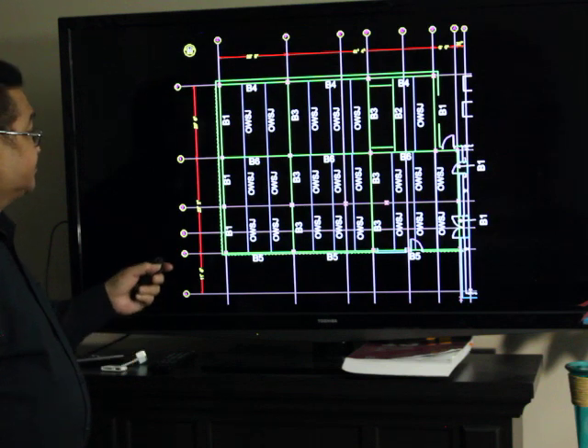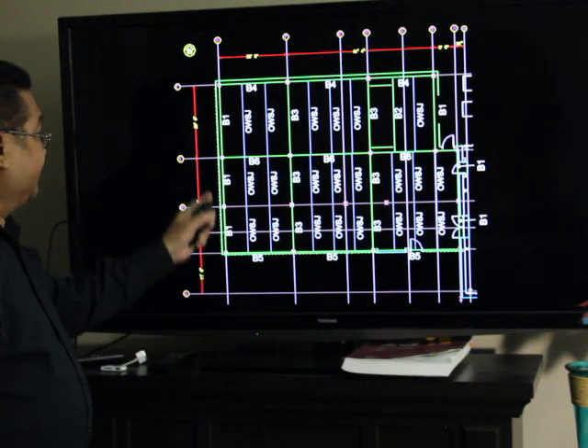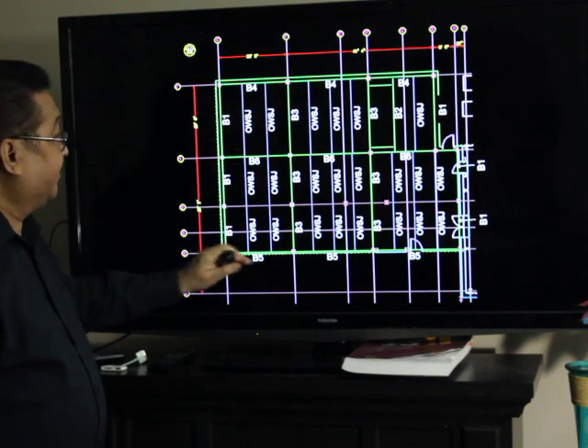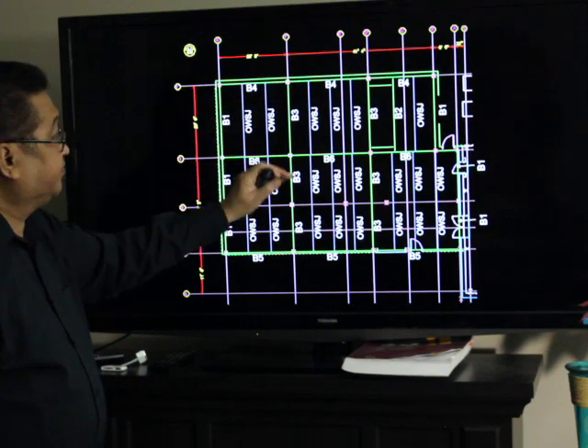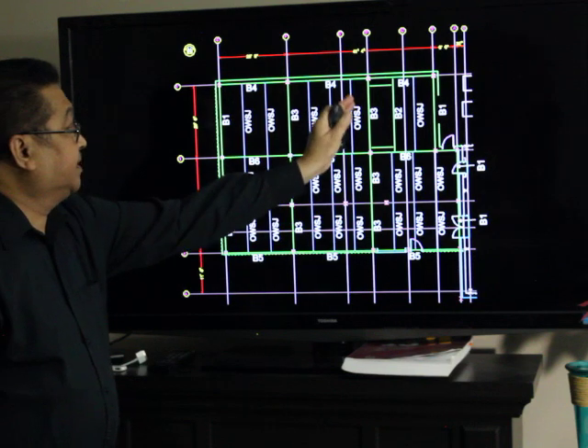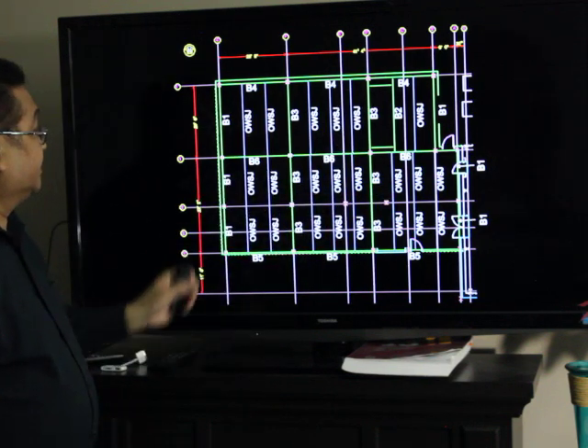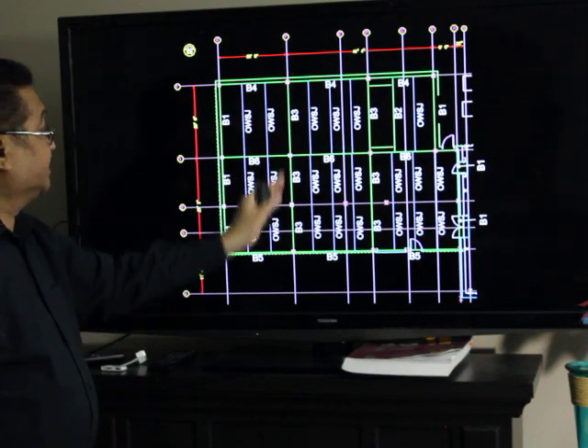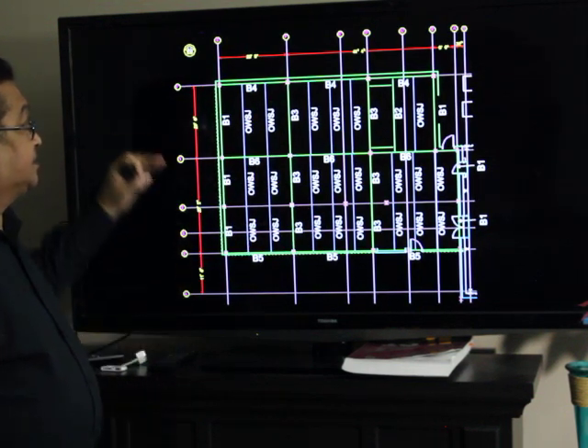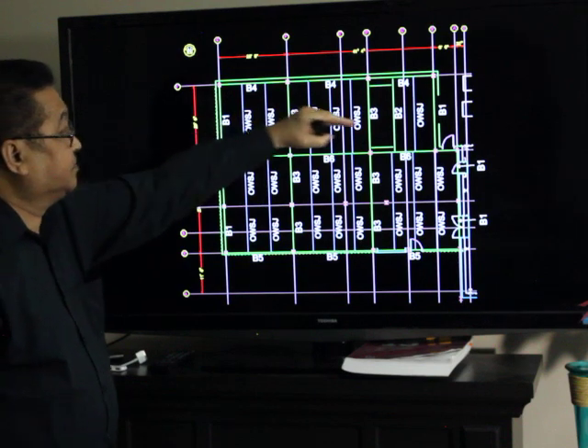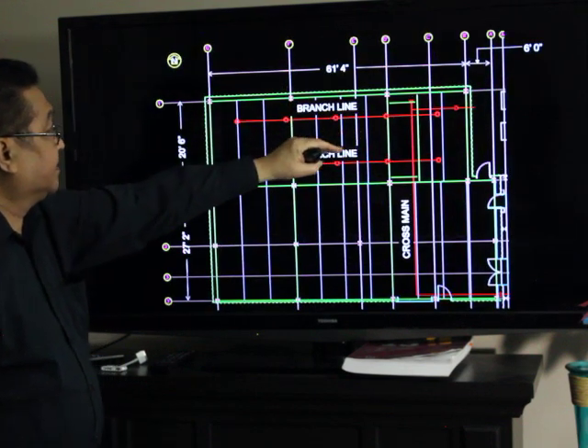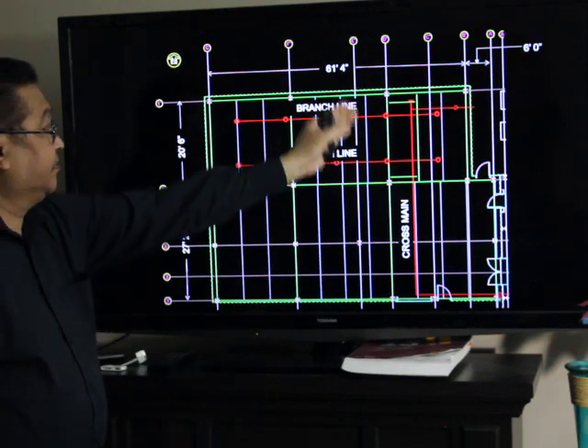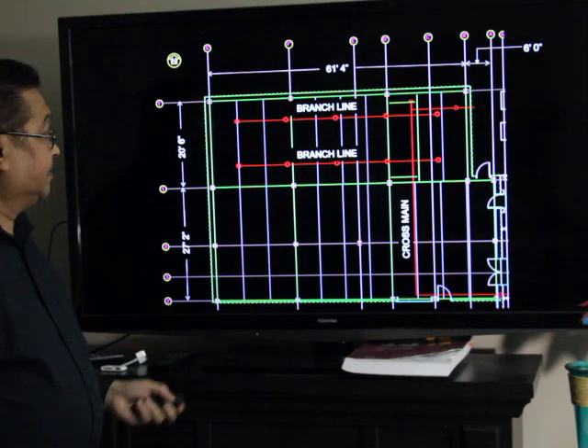So, in this structural drawing, we can see that we have the beams here — B1, B4, B5, B6, and we have B3, B2, B1 in here. And the joists here — you have open web steel joists. So, the branch lines will run perpendicular to the joists here, like this one here. That's why this is the shape. And the cross main will be perpendicular to the branch line.